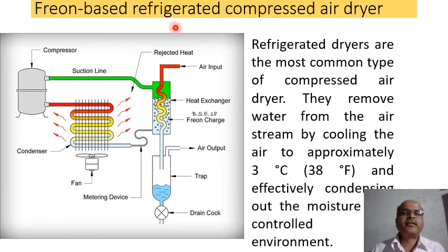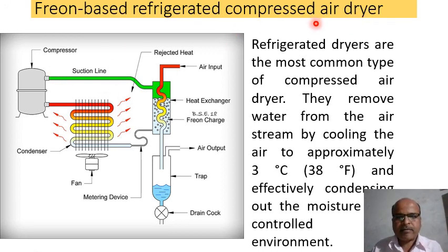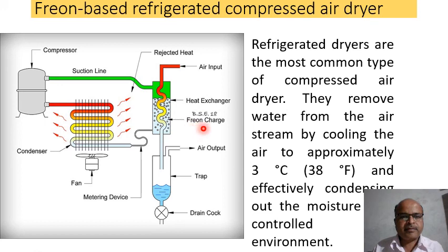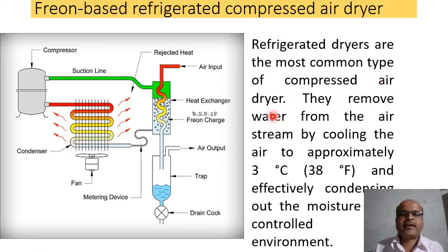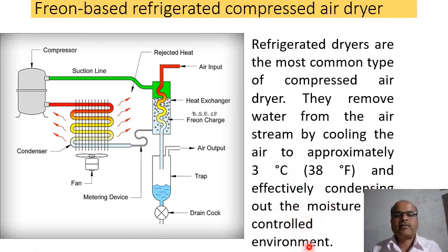Freon-based refrigerated compressed air dryer: The diagram shows compressor suction line, heat rejection, air input, heat exchanger, Freon charge, air output, trap, drain cock, metering device, fan, and condenser. Refrigerated dryers are the most common type of compressed air dryer. They remove water from the air stream by cooling the air to approximately 3 degrees centigrade, effectively condensing out the moisture in a controlled environment.